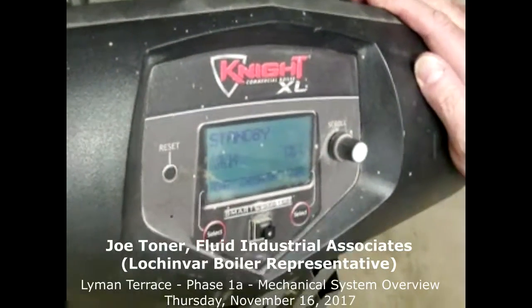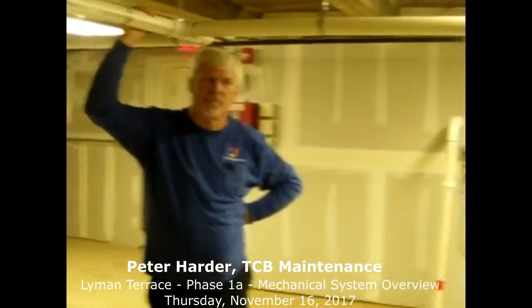Okay. So what things could go wrong that Peter would see? I mean, it'd be like a no heat call, and then you'd come down here to try to figure out why you're not getting heat. If you had a major problem down in the mechanical room, you would have multiple no heat calls upstairs in the apartments. If you get one or two, it may be a zone problem, could be a thermostat issue.